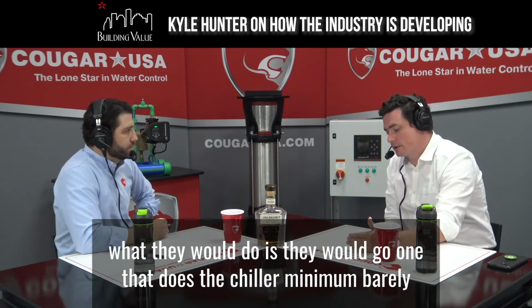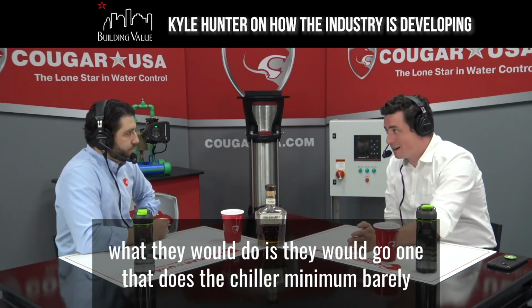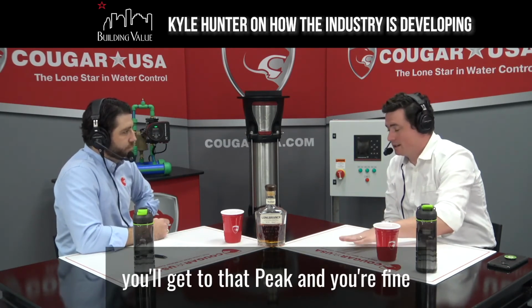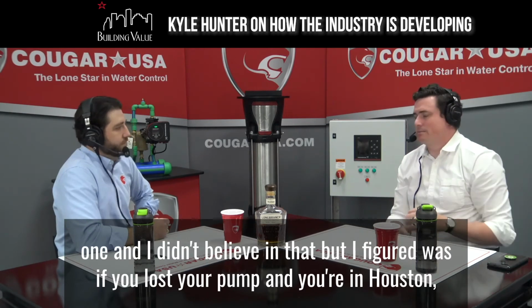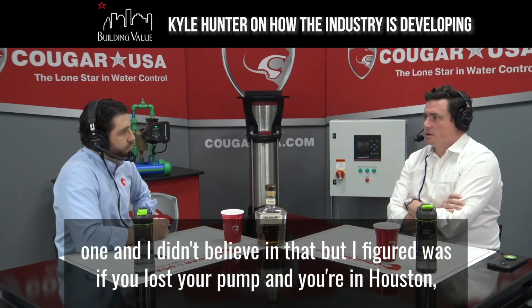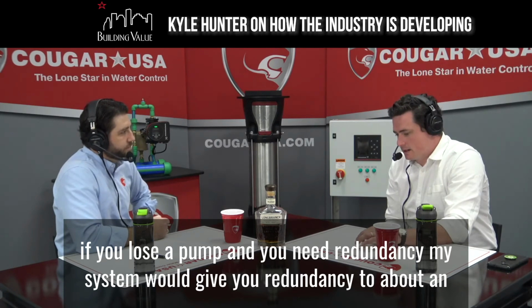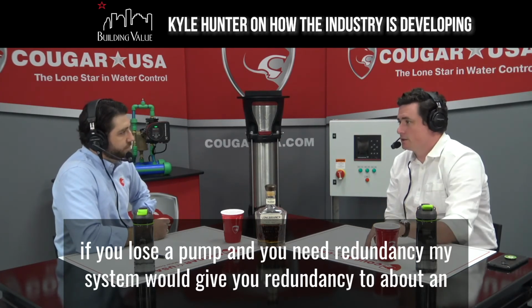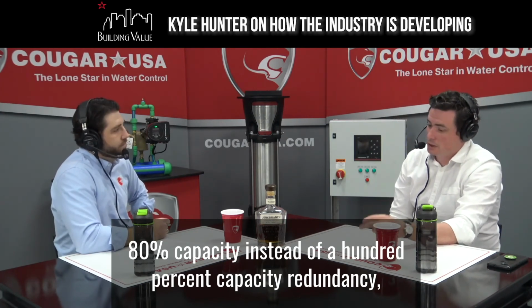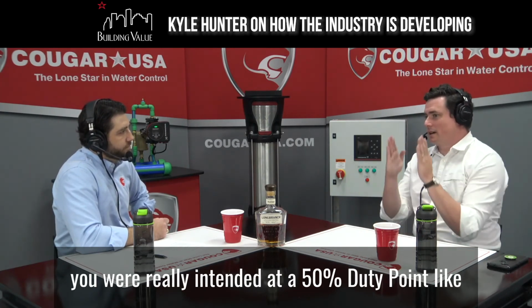And the old engineers, what they would do is they would go one that does the chiller minimum barely, and it does, and you'll get to that peak and you're fine. And then you have a redundant one. And I didn't believe in that. What I figured was if you lost your pump and you're in Houston, Texas, I was like, all right, if you lose a pump and you need redundancy, my system would give you redundancy to about an 80% capacity instead of 100% capacity redundancy.